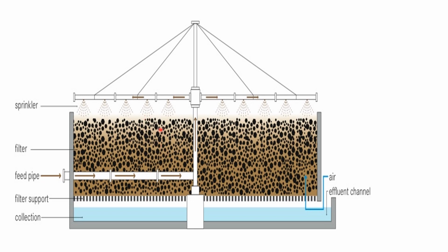Then what is the working of trickling filters? We have a feed pipe, and through this inlet we feed water, mainly sewage water, in order to carry out secondary treatment. We feed sewage water into this trickling filter reactor. So this sewage water enters the trickling filter and moves upwards through this rotating distributor and reaches into the side arms. And side arms contain sprinklers, so this sewage water uniformly falls down into this filtering medium through the sprinklers.